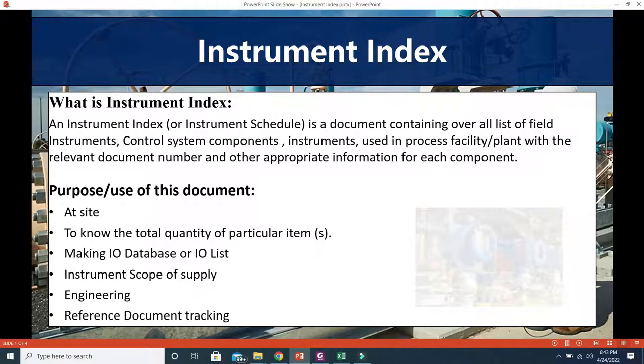Whenever we want to know about a particular instrument, like what is the type of this instrument, what is the IO type, what is the calibration range, and what are the reference document numbers like data sheet, loop drawing number, hookup drawing number, model number, even manufacturer name - if you want to know about any particular instrument, we can refer to the instrument index document. So we can quickly find out the details about any particular instrument from this instrument index.